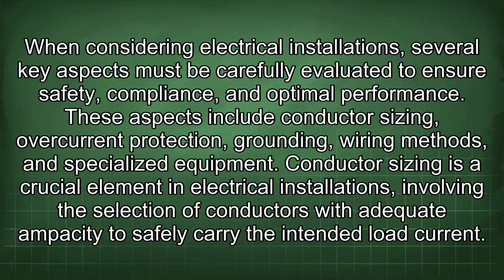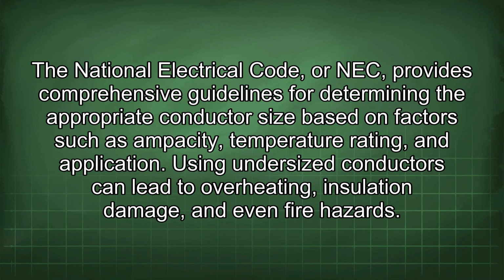When considering electrical installations, several key aspects must be carefully evaluated to ensure safety, compliance, and optimal performance. These aspects include conductor sizing, overcurrent protection, grounding, wiring methods, and specialized equipment. Conductor sizing is a crucial element in electrical installations, involving the selection of conductors with adequate ampacity to safely carry the intended load current. The National Electrical Code, or NEC, provides comprehensive guidelines for determining the appropriate conductor size based on factors such as ampacity, temperature rating, and application. Using undersized conductors can lead to overheating, insulation damage, and even fire hazards.